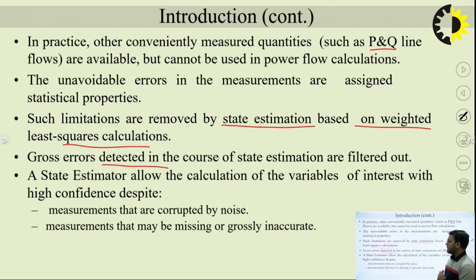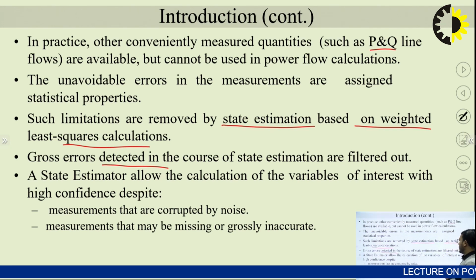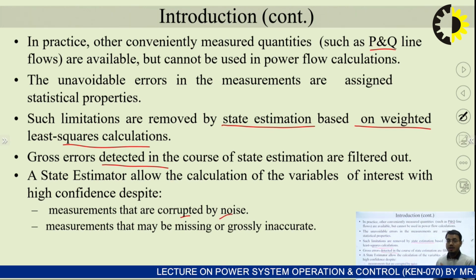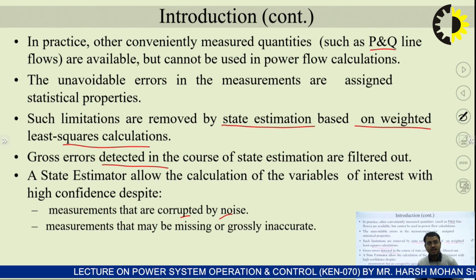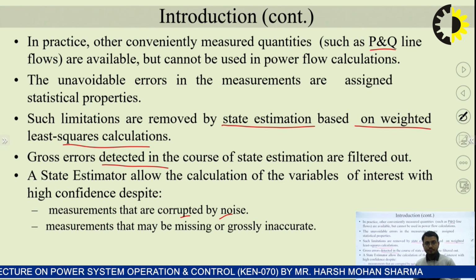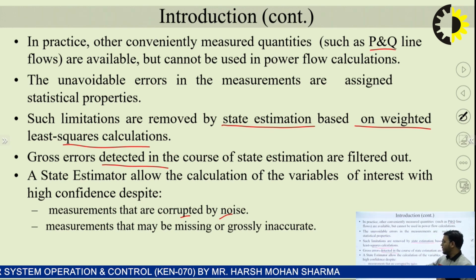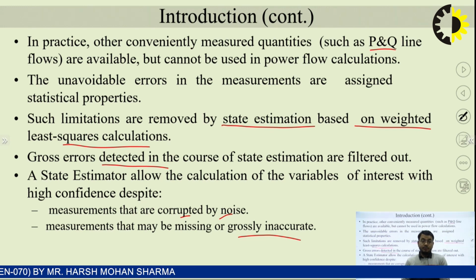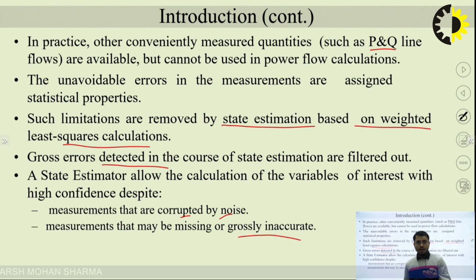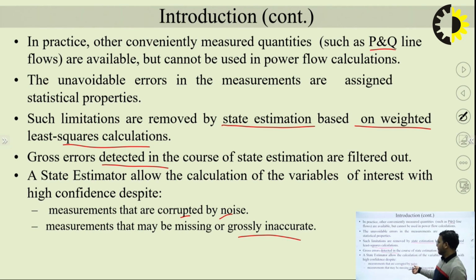State estimators allow the calculation of variables of interest with high confidence despite measurements that are corrupted by noise - since you have a communication system, it is obvious noise will be there. Similarly, despite measurements that may be missing or grossly inaccurate, that is bad data or inappropriate measurements, you can still have accurate calculations through the state estimation process.